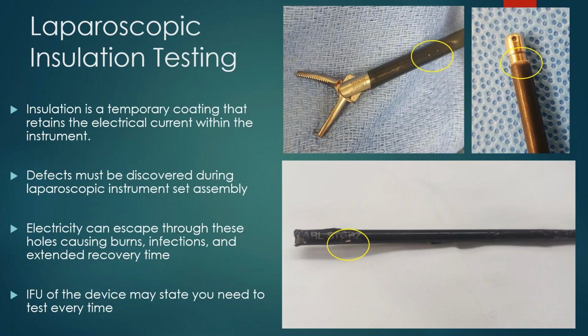So let's get into the insulation testing itself. Insulation is a temporary coating, and it retains the electrical current within the instrument. What I want to stress here is that there's one more word to add to it. It's not only temporary, it's very delicate. Defects must be discovered during laparoscopic instrument set assembly, or depending on the type of insulation test that you may have. You could have sterile ones that are actually being done or checked prior to the procedure. And of course, this depends on your hospital policy and procedure if you are using those.